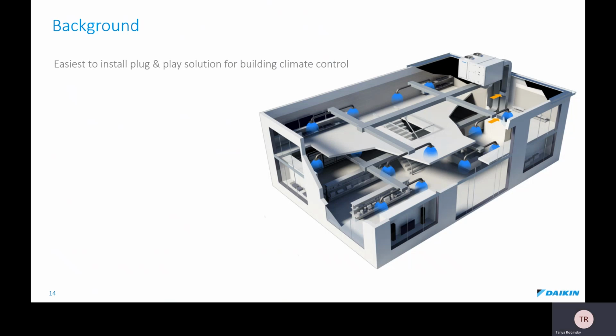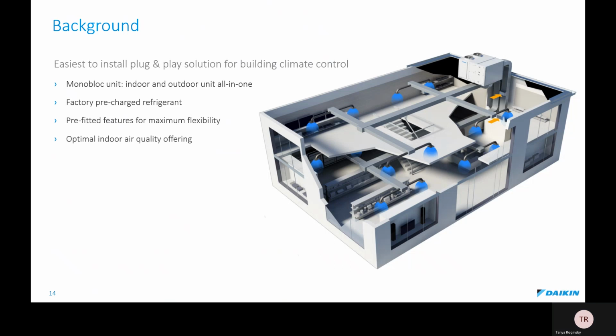Rooftops in general are an easy to install solution for optimal climate control. They are monoblock units with no additional piping or connections to be made on site. The units come pre-charged with refrigerant, so no additional charge is required. There is a set of pre-fitted features that allow maximum flexibility, available as standard. The unit can meet fresh air and filtration requirements for any application where indoor air quality is critical. There are also multi-directional air supply and return possibilities. It is easy to service the unit.